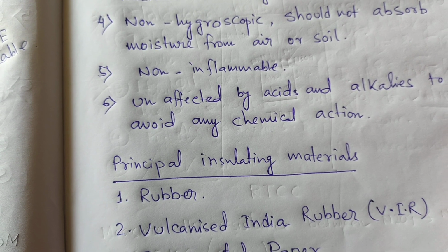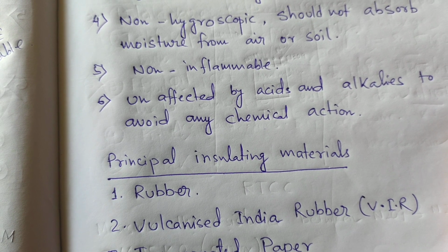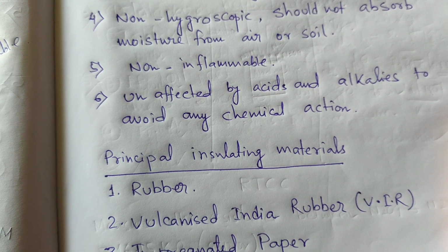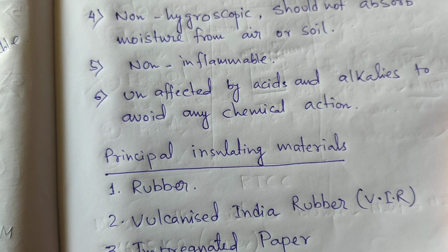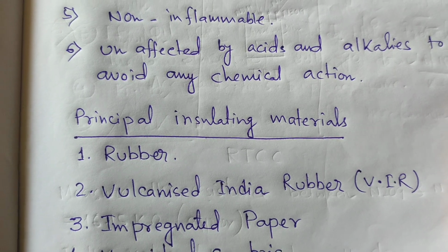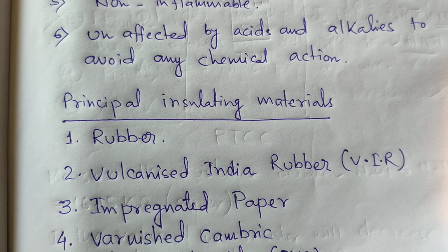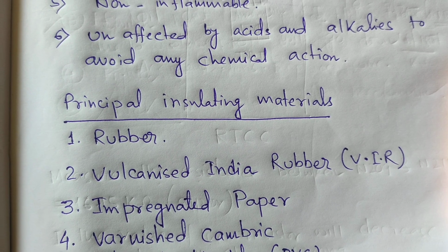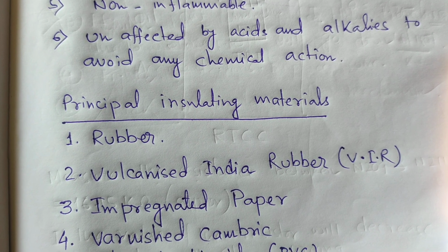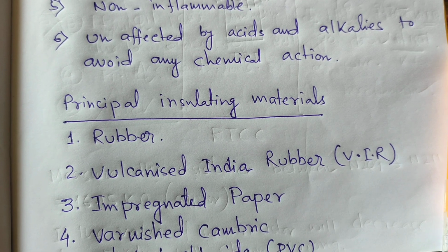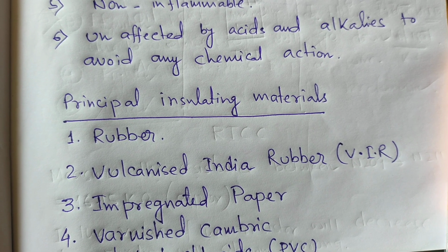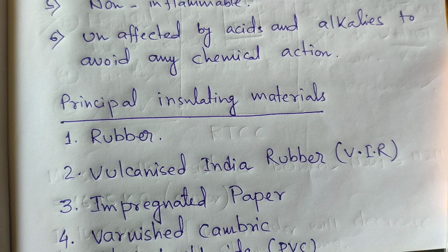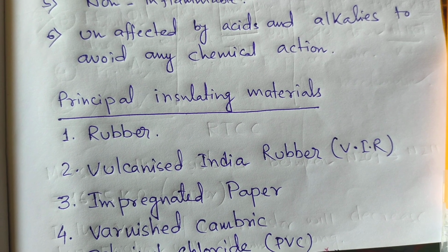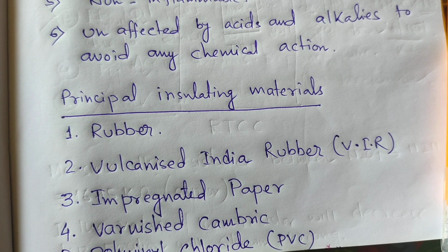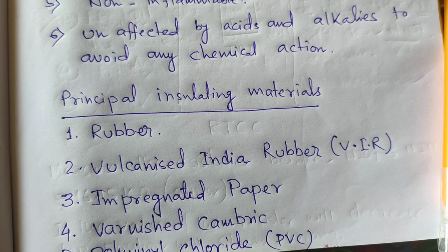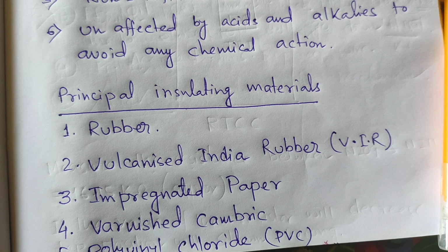Pure rubber has reasonably high insulating properties. Also, rubber insulation has a few drawbacks. What type of drawbacks does it have? It absorbs moisture, the maximum safe temperature is low, about 38 degrees Celsius, and it is soft and liable to damage due to rough handling and aging. So the next is vulcanized India rubber.